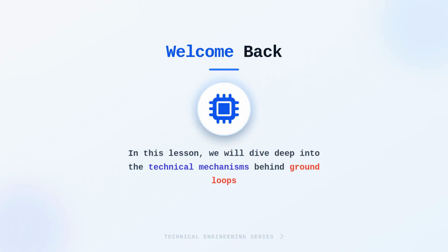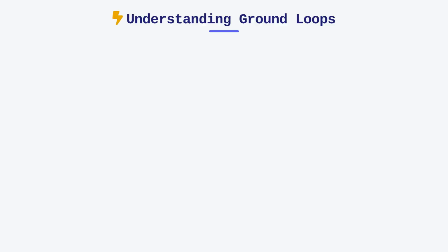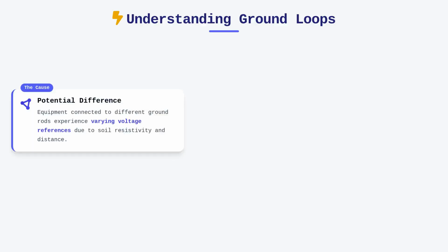Welcome back. In this lesson, we will examine the technical mechanisms behind ground loops and the rigorous methodologies required to prevent their damaging effects. A ground loop occurs when two or more pieces of equipment are connected to the same signal path but reside at different ground potentials. In an ideal scenario, all points within a facility's grounding system share an identical voltage reference, essentially 0 volts relative to the earth. However, in reality, ground rods driven into different locations often exhibit varying potentials due to soil resistivity changes, distance from the main service entrance, or high impedance connections.